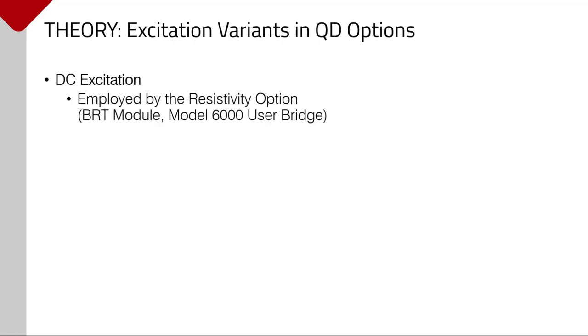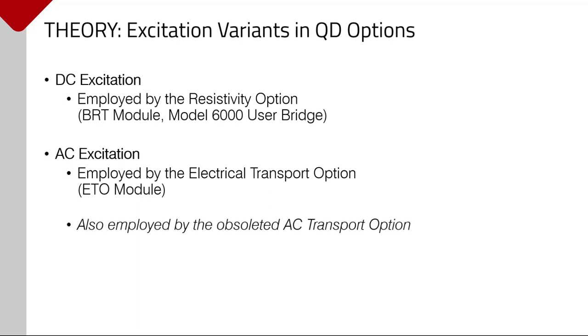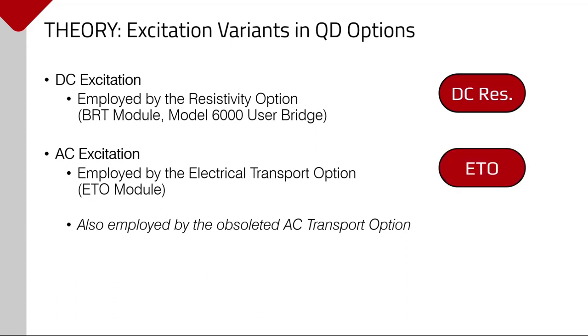Quantum Design offers two measurement options which can quantify a sample's electrical resistance. We will compare and contrast these two tools throughout the talk, but the basic difference is the sample excitation mode. The resistivity option essentially employs a DC excitation. The hardware used for this is either the BRT module in CAN-based systems, or the user bridge card in systems with the legacy Model 6000 controller. The electrical transport option, or simply ETO for the remainder of the talk, in contrast uses an AC excitation and a more complex detection scheme. A similar setup was used by the now-obsoleted ACT for users familiar with that legacy option.